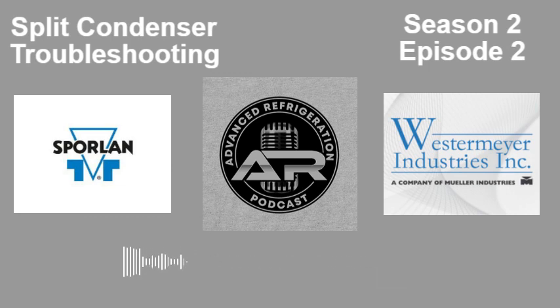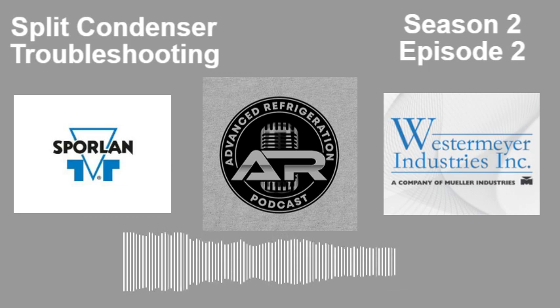Gotcha. Yeah. So, and then at the same time, Walmart uses a bypass solenoid on the holdback. That's how they're able to get that pressure down. They actually bypass the holdback valve. They do this on all their stores pretty much. So there's a solenoid on the holdback valve. They're bypassing that holdback valve so they can get that pressure down.